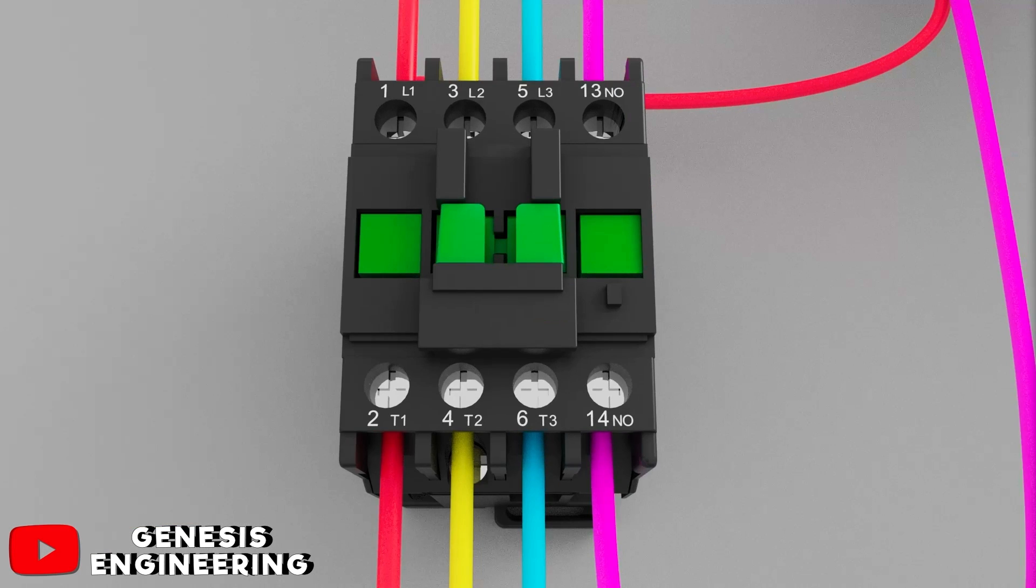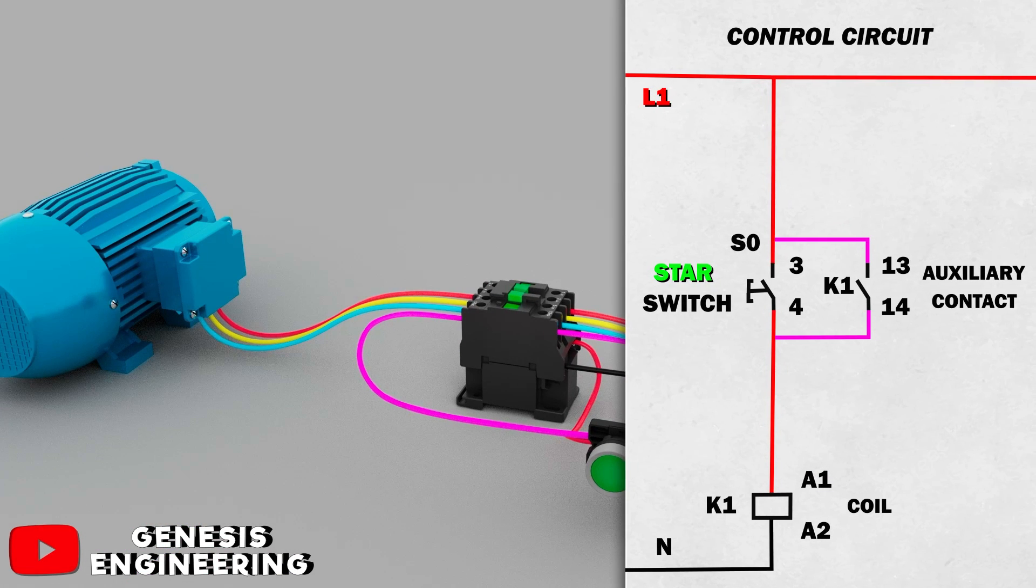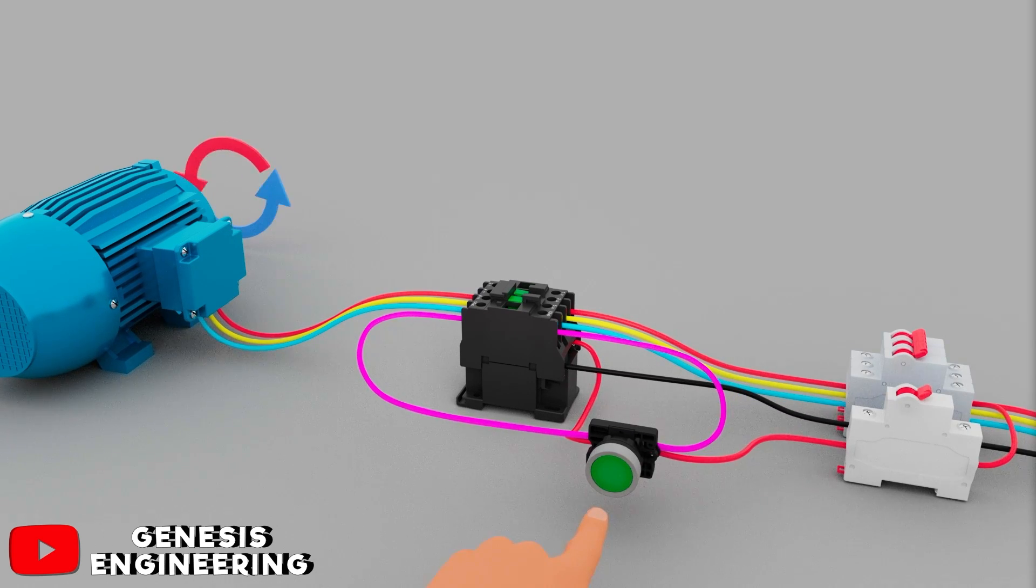In this way, we made a parallel path for the energy to pass, which keeps the contactor on without the button being pressed, using the contactor's auxiliary contacts. Now when we release the button, the contactor will stay on because of the contact holding, because it now has a parallel path for the power to pass through and keep the motor running.